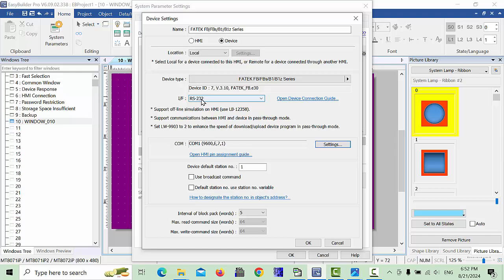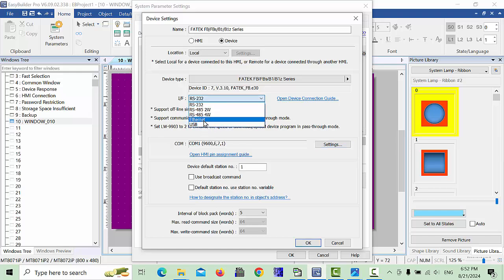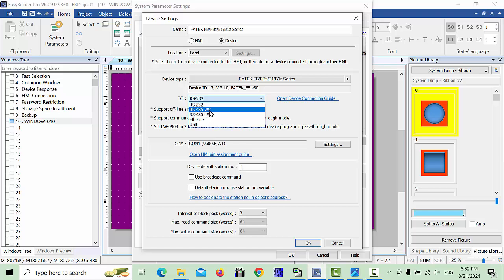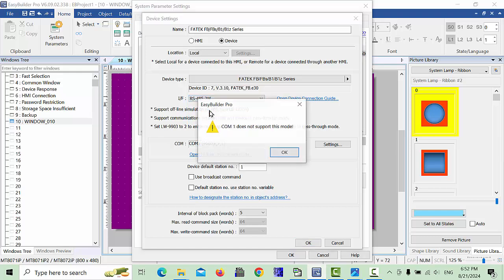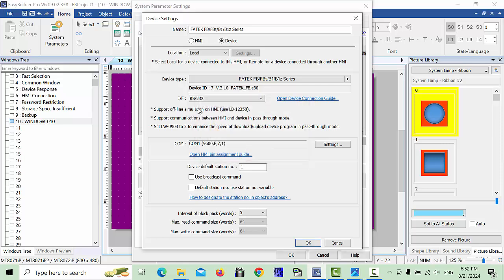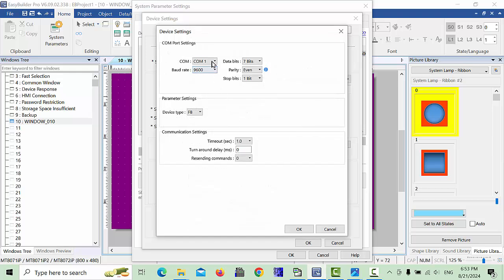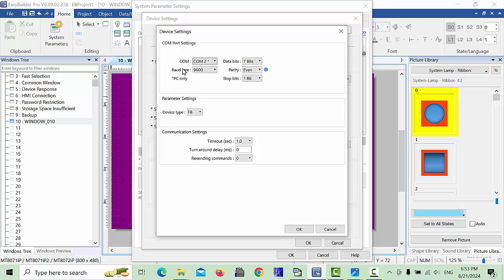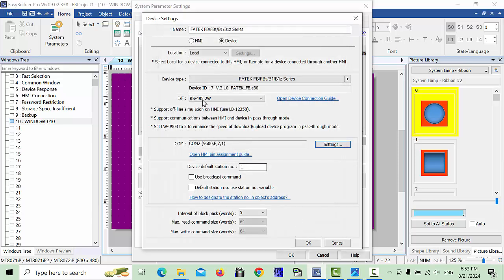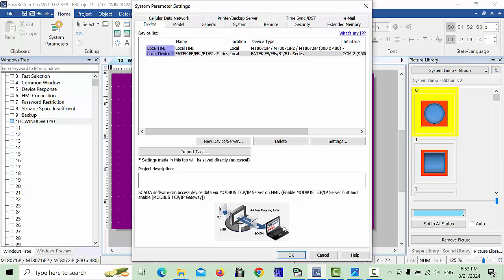Here you can use RS232, USB type, Ethernet type, RS485 four wire, or RS485 two wire. I am using RS485 two wire, so select this. But before, you have to make the setting. Choose COM2 because COM2 is the RS485 two wire. Click OK and it will automatically show RS485 two wire control. Then click OK and your connection will be successful with RS485.